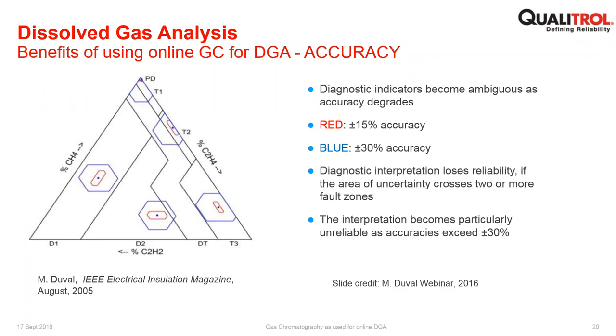If we look at a slide that was very generously provided by Michel Duval to Qualitrol, this shows the implications of reduced accuracy. At plus or minus 15%, which is typical of a lab, you will see that there is in fact a range of locations where the coordinate points can be. And depending on that range, you may or may not find yourself in a single diagnostic space. And certainly if you increase to plus or minus 30% accuracy, which is typical if the sample collection is of poor quality, you may find yourself moving from one diagnostic space to another, essentially resulting in the possibility of false diagnosis.